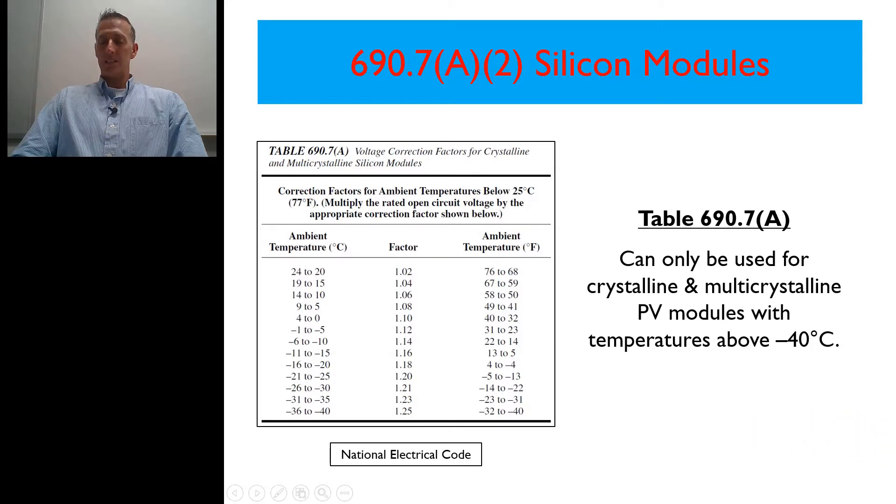What that means is whatever voltage, the open circuit voltage the modules are rated at, we would multiply that by 1.2. So if we had a 40 volt module, and we had 10 of those in series, so it's 40 times 10 is 400.